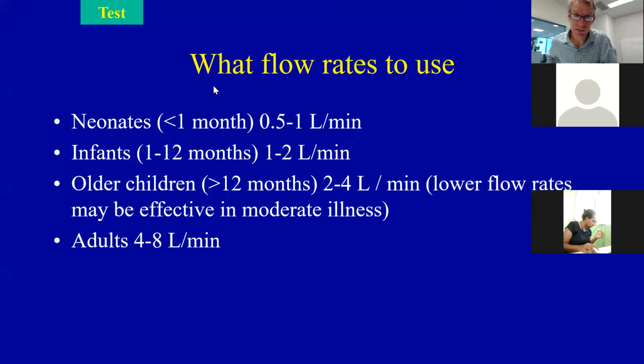The flow rates we use, I think, will be familiar to you. So neonates, 0.5 to 1 litre. Remember that infant I showed you earlier on, she just needed 0.5 litre of oxygen. But some young infants who've got severe pneumonia, they may need 1 to 2 litres per minute in the first 12 hours of their treatment. And older children, they may need up to 2 to 4 litres per minute. And adults, they may need 2 litres per minute, or sometimes 4 litres per minute, or even up to 8 litres per minute. And this is very important.